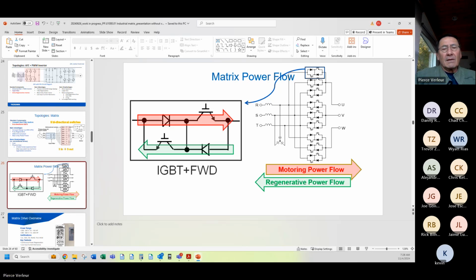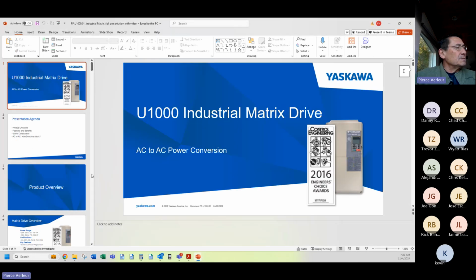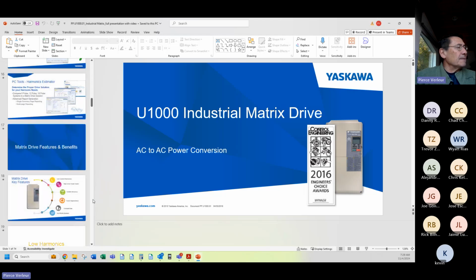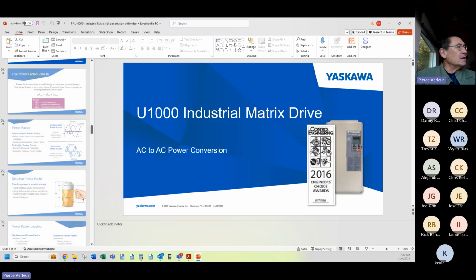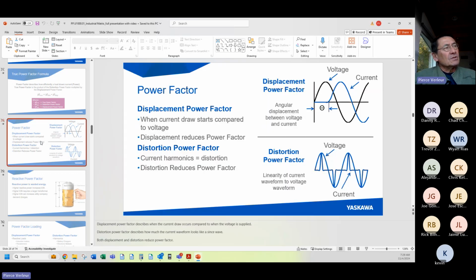Now, for those of you that don't understand power factor, I will spend a little bit of time explaining that, because that's one of the major benefits of matrix technology. Power factor consists of 2 components: displacement power factor, where the current in time lags the voltage. Here's the voltage starting up on its sine wave. This is single phase. Obviously, most power is 3-phase. And here's the current lagging it. When does that occur? That actually occurs when a motor is connected directly to the line via a contactor.